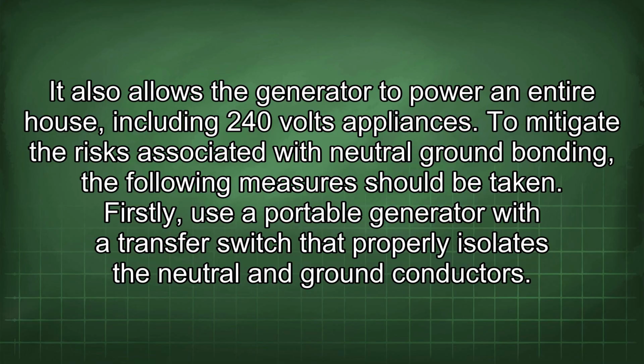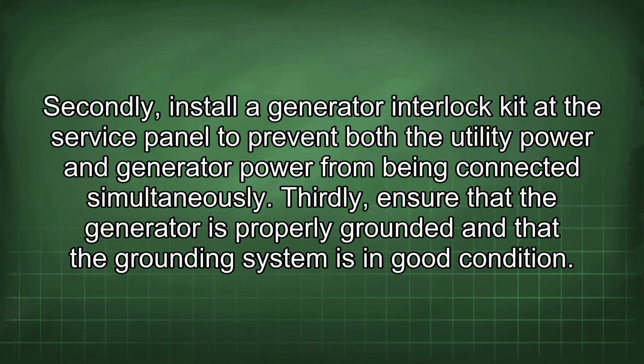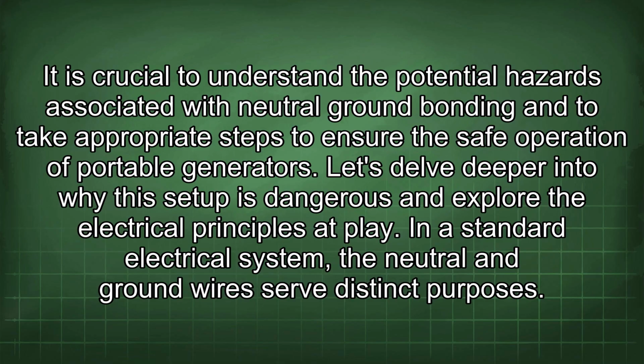To mitigate the risks associated with neutral ground bonding, the following measures should be taken. Firstly, use a portable generator with a transfer switch that properly isolates the neutral and ground conductors. Secondly, install a generator interlock kit at the service panel to prevent both the utility power and generator power from being connected simultaneously. Thirdly, ensure that the generator is properly grounded and that the grounding system is in good condition. It is crucial to understand the potential hazards associated with neutral ground bonding and to take appropriate steps to ensure the safe operation of portable generators.